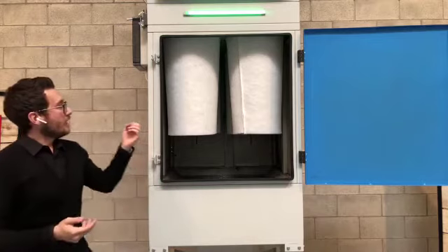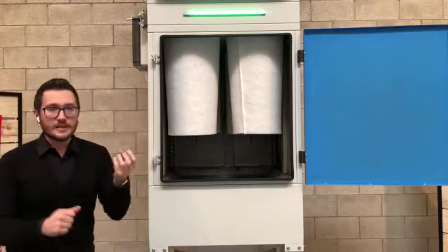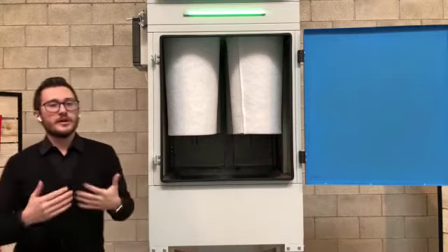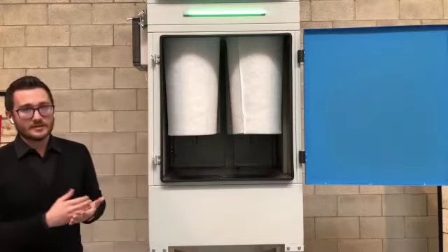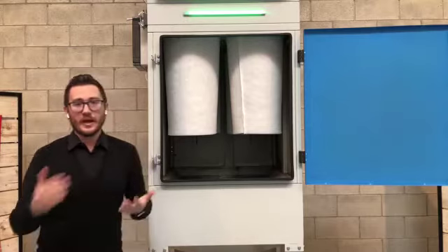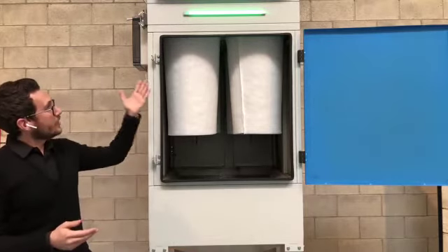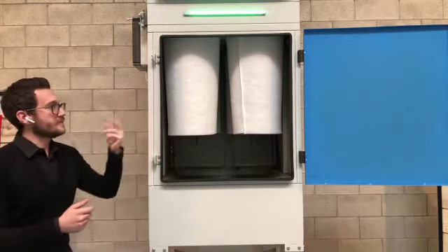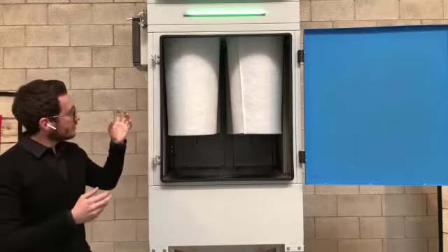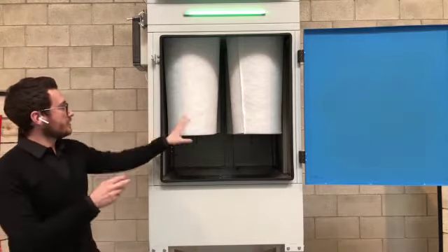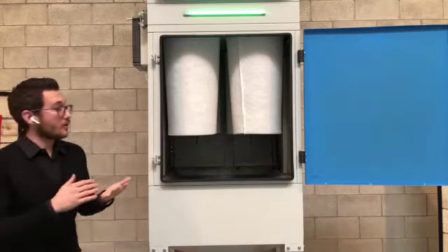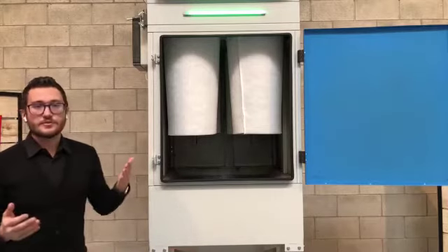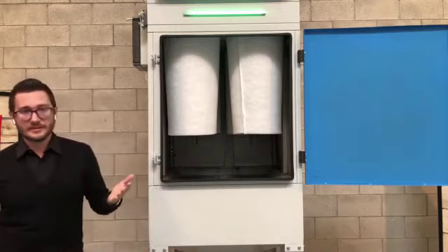Okay, so you have basically the actual data. You know when the filter is getting clogged and when the filter is starting to have some problems, and maybe you can start scheduling, you have to start planning some maintenance. So when you have this accessory on the filter, you can visually see when it's time to do the maintenance based on the pressure differential. So when the cartridges start getting clogged, obviously the delta P, the difference in terms of pressure, increases. So you know that you have to start planning a maintenance.